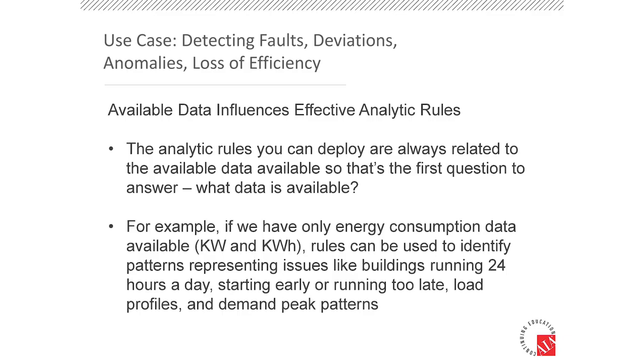The reason is they were able to run analytics that looked at the schedule versus the consumption pattern and say, hey wait a minute, this building we're committed to 7 a.m. to 7 p.m. Why are we starting up at 3 a.m. and running till 11 at night? Or why is there no fluctuation? Because somebody overrode the systems, right? Maybe they moved in new tenants over the weekend or at night or whatever. All these good reasons that may never get corrected.